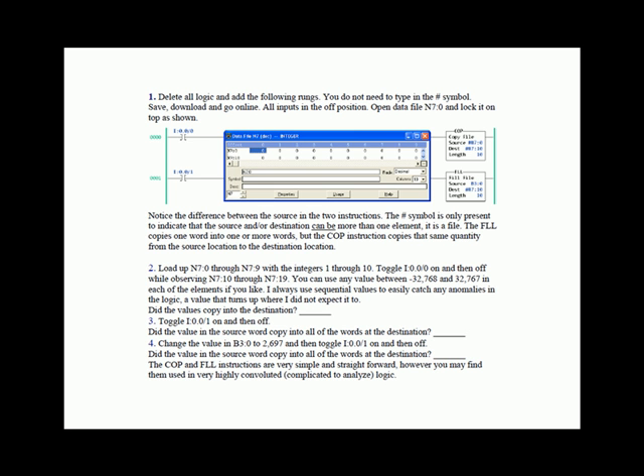The FLL or fill file instruction copies one word into one or more words, whereas the copy instruction copies the same quantity from the source location to the destination location. I had you fill up the integers N7:0 through N7:9 with integer values one through ten.